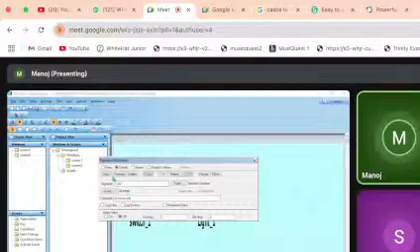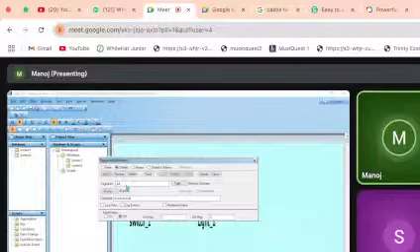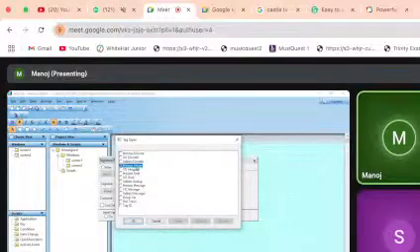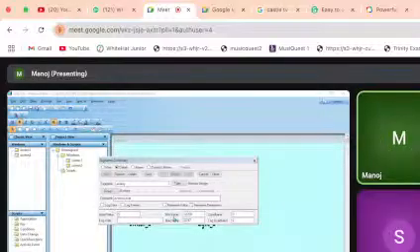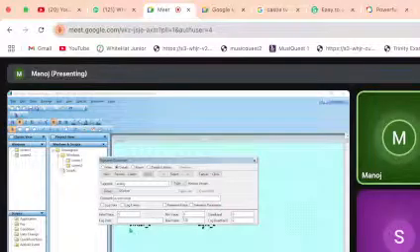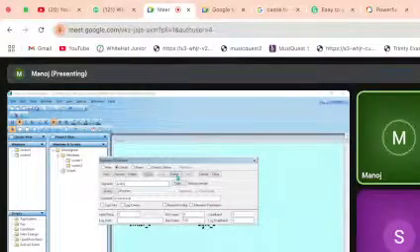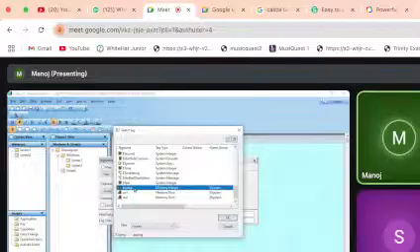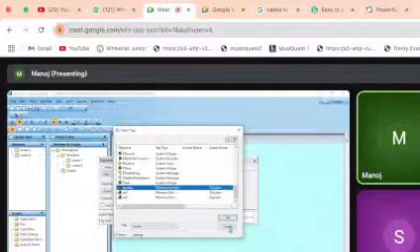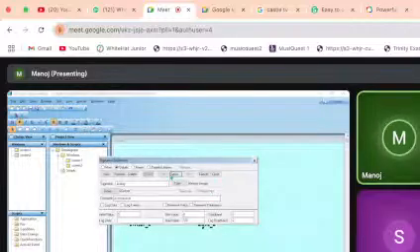Now I am creating an analog tag. I will just name it Analog. There you should select which type of tag. For analog, I can select memory integer also. Both are similar. The minimum value and maximum value we can give there: 0 and 100 I'm giving. Then you can save that. So three tags I have created. If you want to see what tags you have created, you need to go to the Select option. Here you can see that in the previous case it is not there. Now it came here because we have now created all the tags. Clear? Tag creation, any doubt?